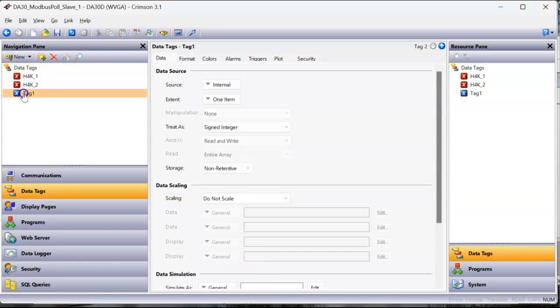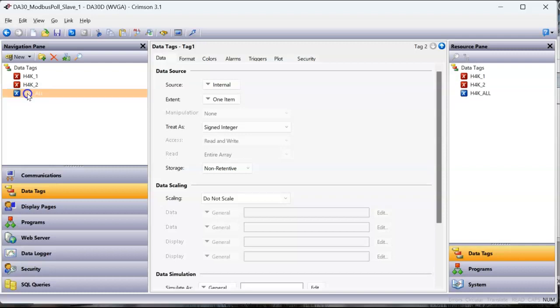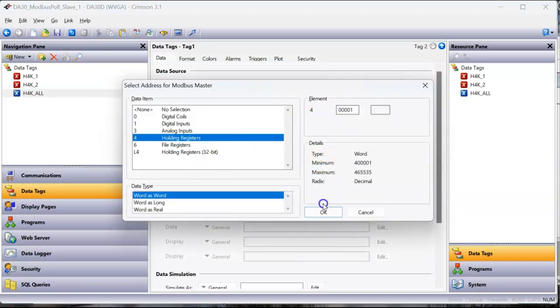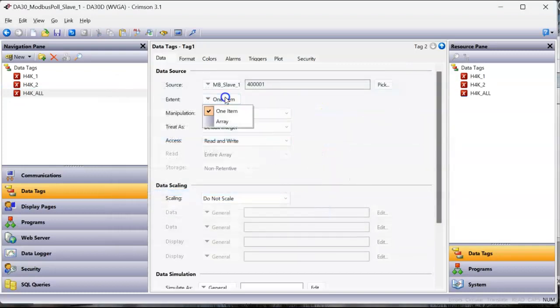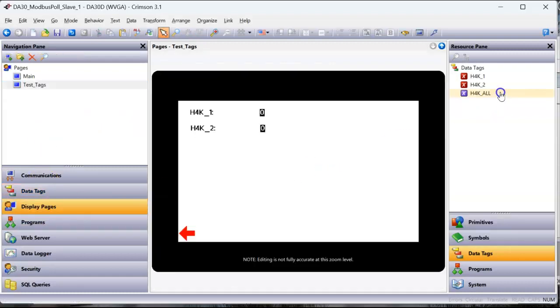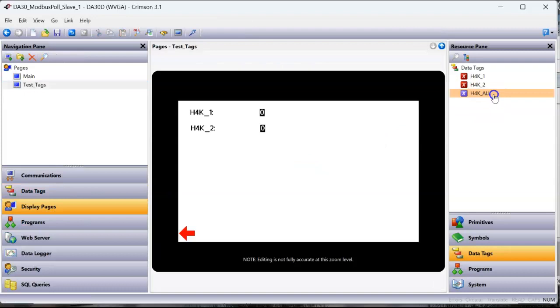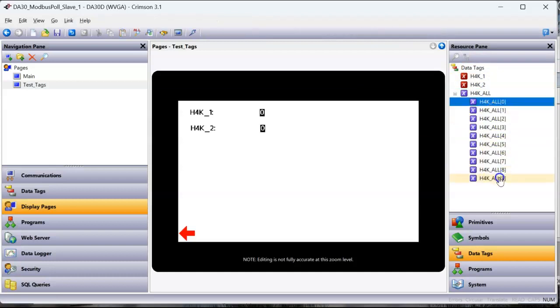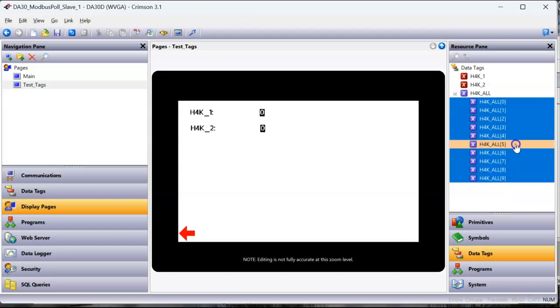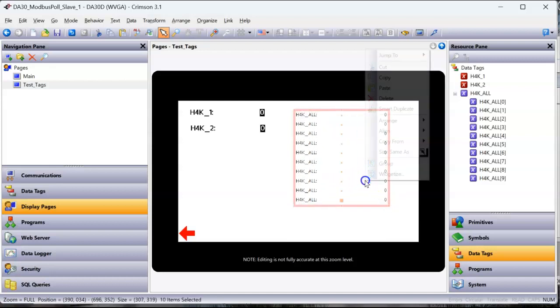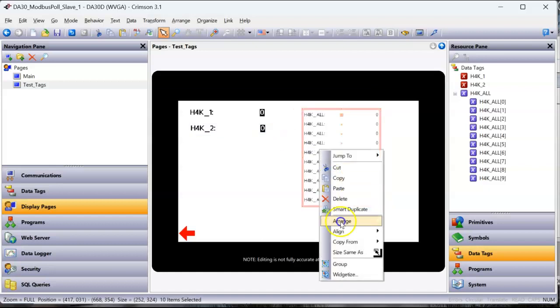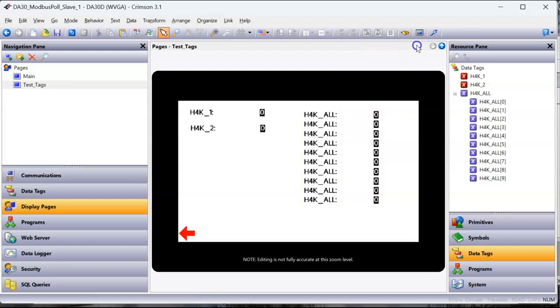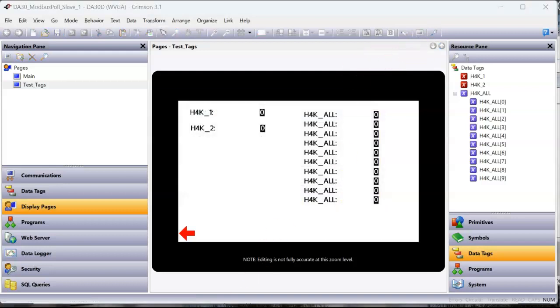I'm going to create another new tag here. We'll just call this guy H4K_all. And the reason I'm doing all is because I'm going to make this guy go to the first one, 40,001, but I'm going to make it be an array of 10 elements. So now this guy should show all 10. So if I go over here to display pages, go ahead and click over here on the right side. If you either click this button or you can right click and do toggle array. Now I can see all 10 elements. So I'll click on the first one, element zero, hold down a shift button, click on the last. I've highlighted them all. I'll drag out all these guys like this and I'll go ahead and make them a little bigger like that. And I'll right click. I'll do same size as one of these. And I'll say copy from all formatting. One of these guys. Let's try this out.